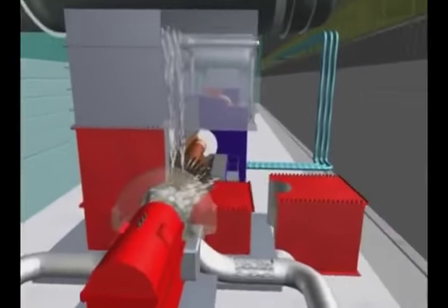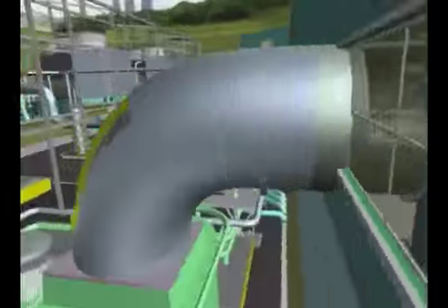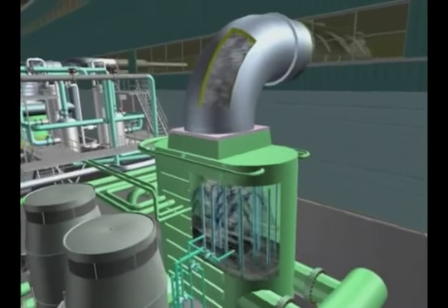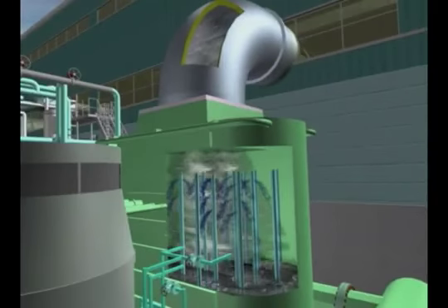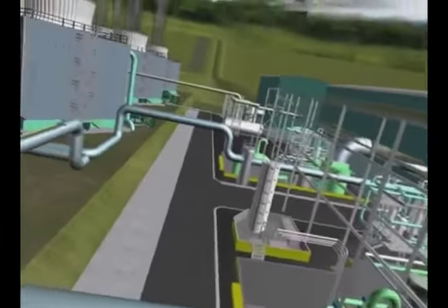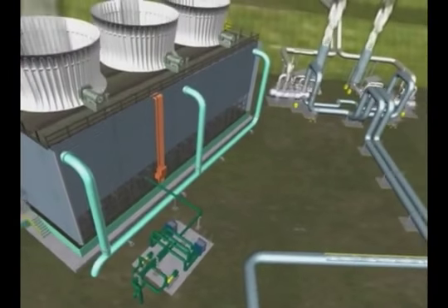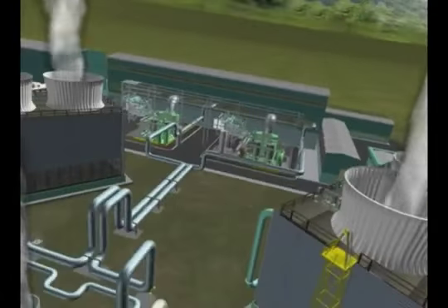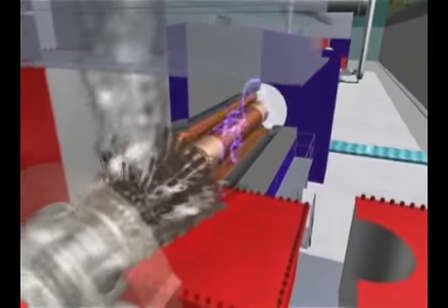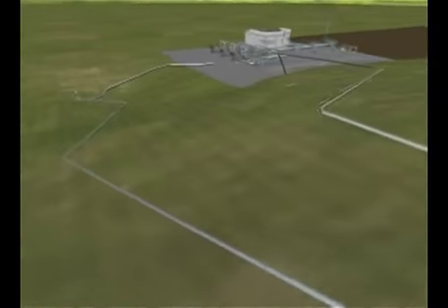The geothermal steam, after completing its function of moving the turbine, goes to a condenser, where it is converted again to water by means of internal cylinders, which inject water so steam can be condensed. Once the steam is converted to water, it is pumped to the cooling towers to lower its temperature. Part of the water is used to cool some of the equipment in the power plant, and the rest is re-injected back to the subsurface.